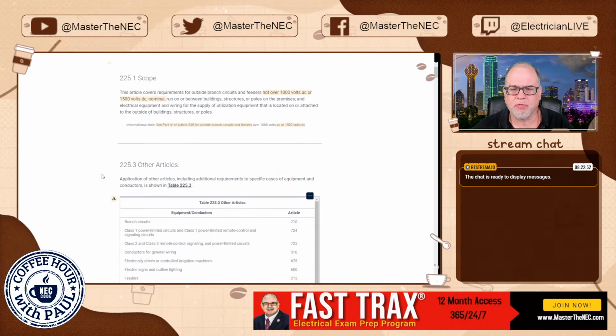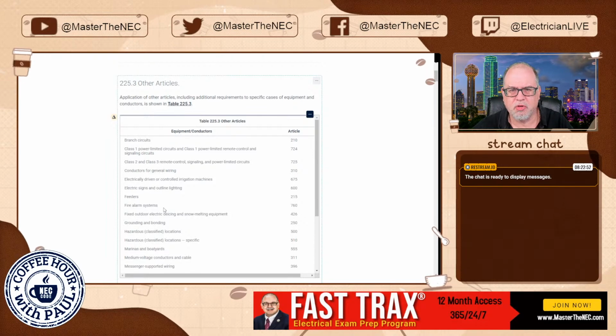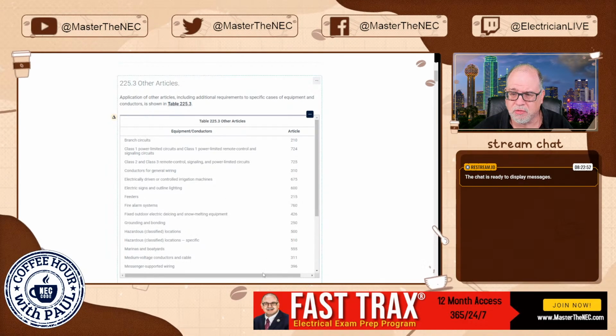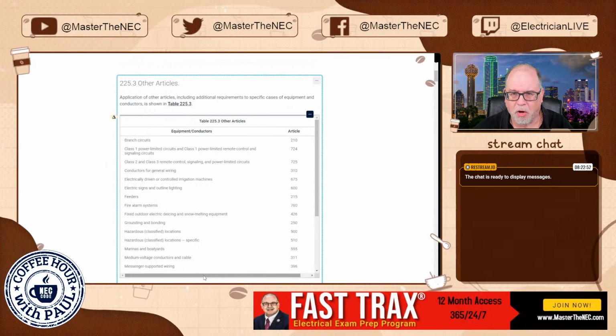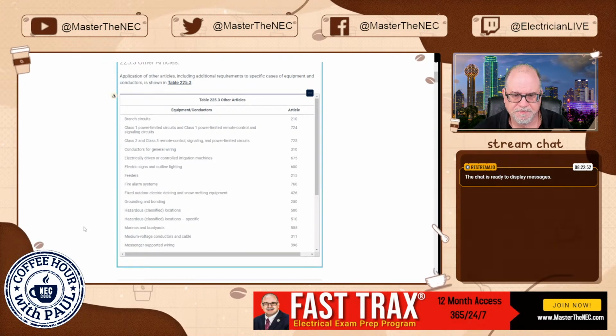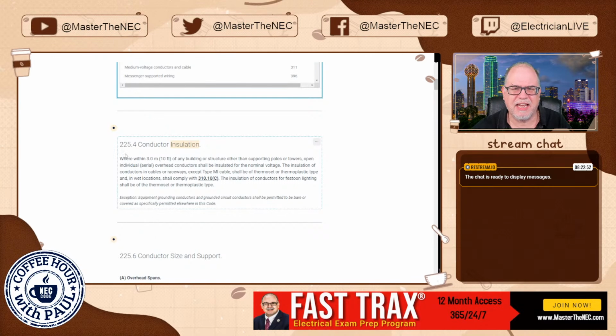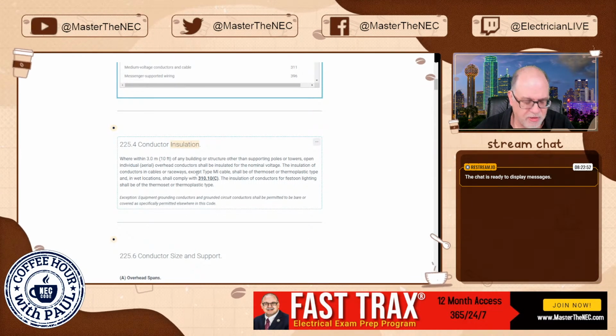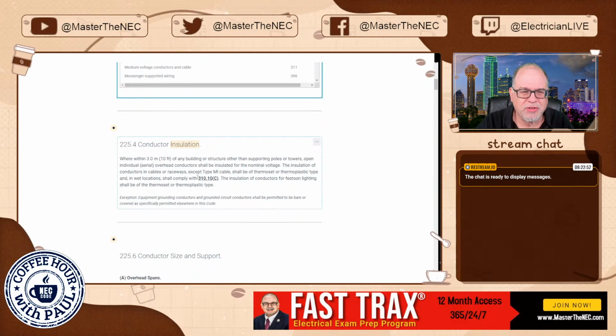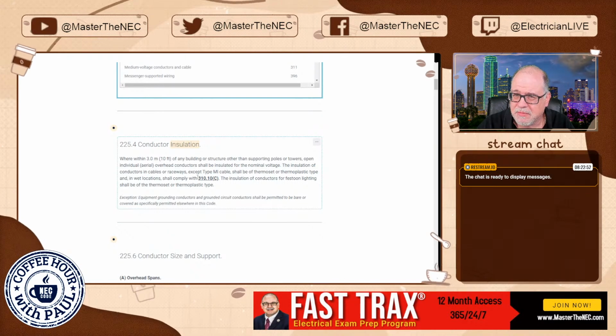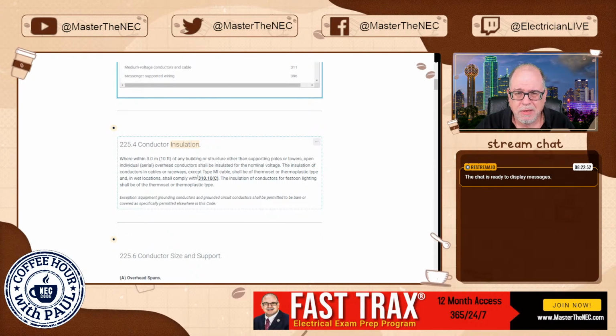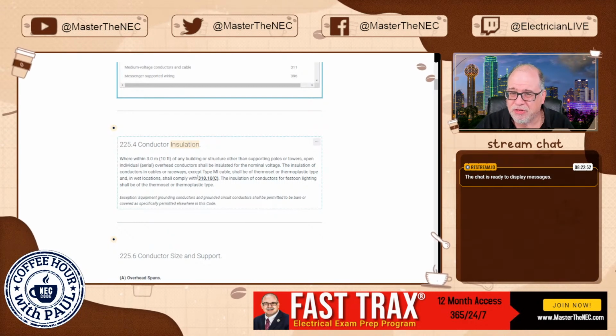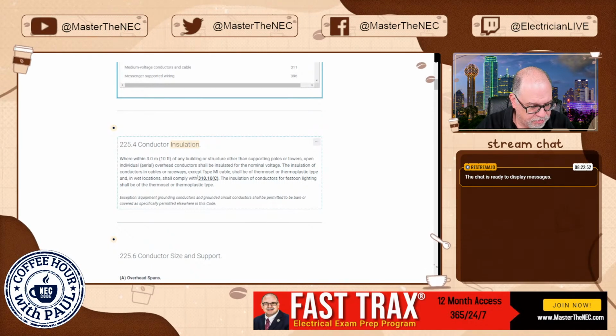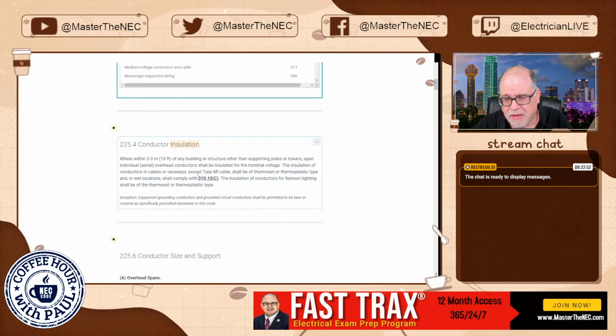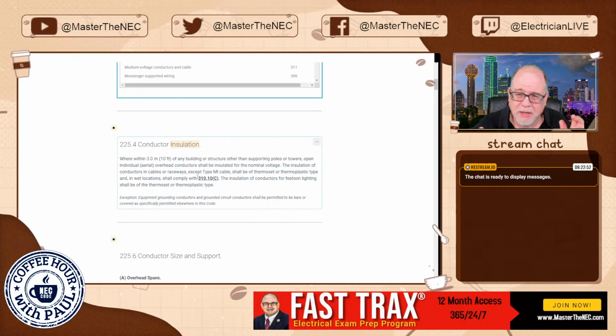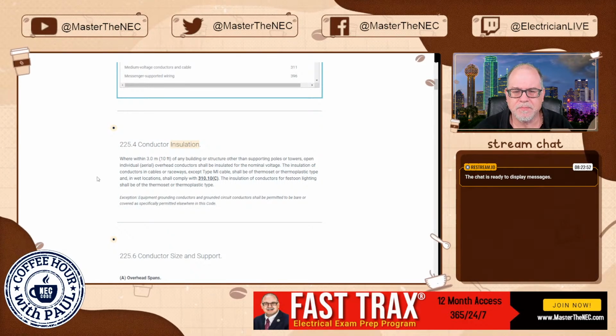So, all right. Let's move through and look at some changes here. Again, 225.3 is just going to give you other articles that you need to be aware of that are also in addition to what we're going to be covering in 225. Okay. And you'll see little changes like 225.4 says conductor insulation. It used to say conductor covering, but that wasn't totally accurate because covering is something like a nylon that gets extruded over something like THHN, and that's a covering. The insulation is what we're talking about here. So we had to change that from conductor covering to conductor insulation. Not significant in the realm of, ooh, big change, but it clarifies what we're talking about, all right?